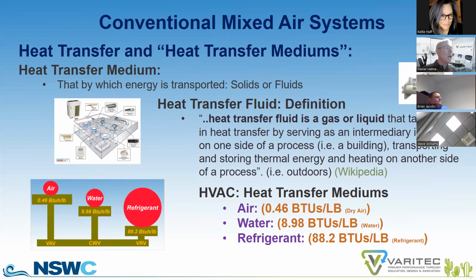First of all, in order to have heat transfer, you have to have a heat transfer medium. And there are 3 mediums of heat transfer available in our industry. They are air, water, and refrigerant. We need this medium so that we can transport energy from point A to point B. Air is not a dense heat transfer medium, so air can only move 0.46 BTUs per pound of air. Water is more dense, so it can move 8.98 BTUs per pound of water. And refrigerant, it's very dense and it can move 88.2 BTUs per pound of refrigerant.